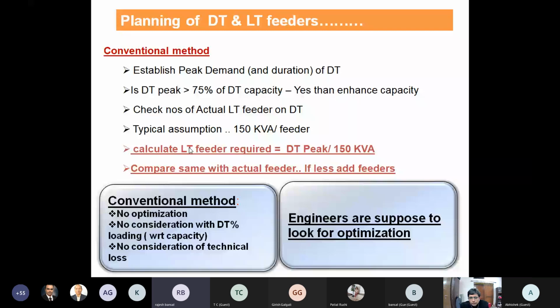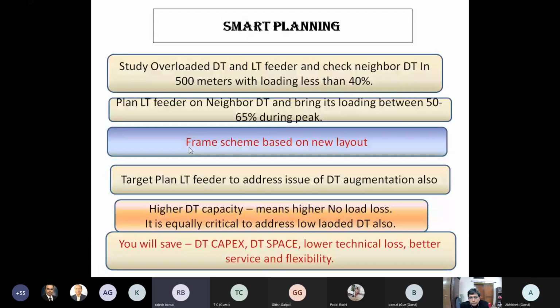You can see that's the conventional method versus smart planning. The smart planning is, as I said, if there is overloading, we look for what is underloaded below 40%, then look for the feeders, and it's better to lay a feeder from the one which is underloaded rather than the one which is overloaded and putting a new transformer, adding no-load losses, especially in winter when there is no load.